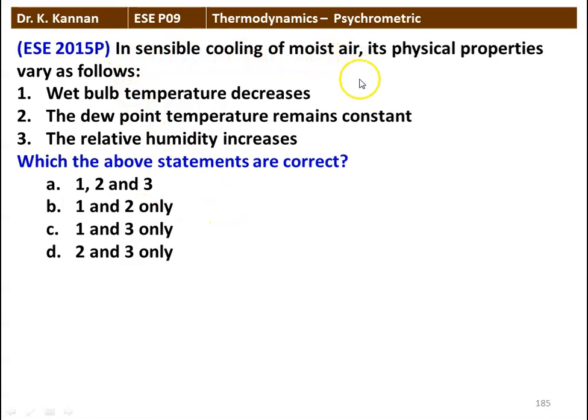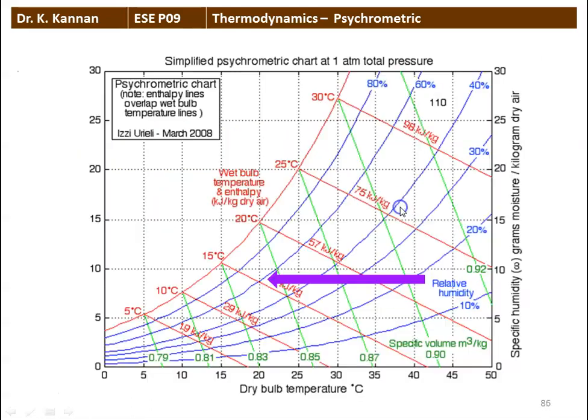Next question: in sensible cooling of moist air, physical properties vary as follows — wet bulb temperature decreases, dew point temperature remains constant, relative humidity increases. The correct answer is all three statements are correct. During sensible cooling, dew point temperature remains constant along a horizontal line; wet bulb temperature decreases from approximately 23 to 22 degrees; and relative humidity increases from approximately 20% to 80%.